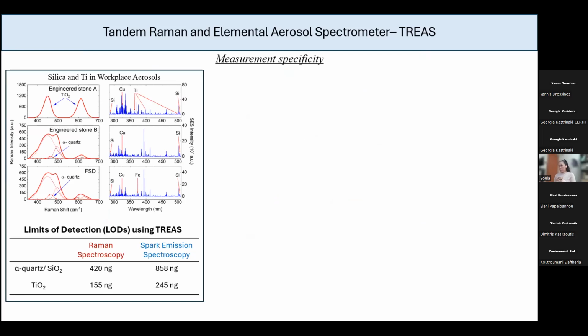These are some results that we got during its evaluation, that also show the importance of having both analytical techniques in one instrument. First, we used it to identify and quantify some compounds of interest for NIOSH, which are the silica and the titanium dioxide. We used two different engineered stones and fracking sand dust. In the first case, we see the two characteristic peaks. The red lines are the Raman spectra, and the blue lines are the spark-emission spectra. So in the first case, using the Raman spectra, we see the two characteristic peaks that we get when we have the titanium dioxide. We also see the titania in spark-emission spectroscopy, along with some other elements.